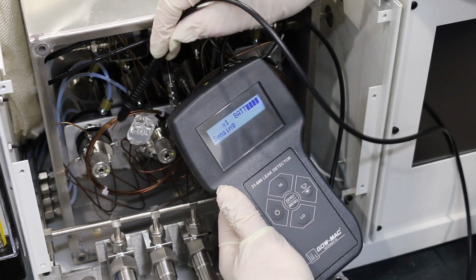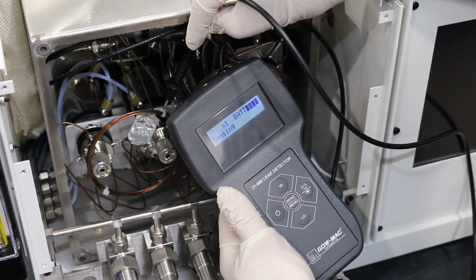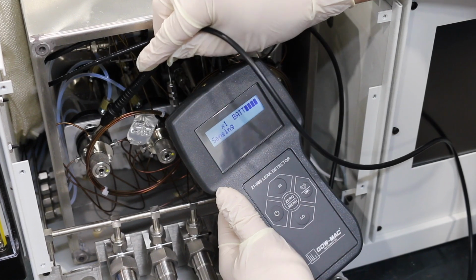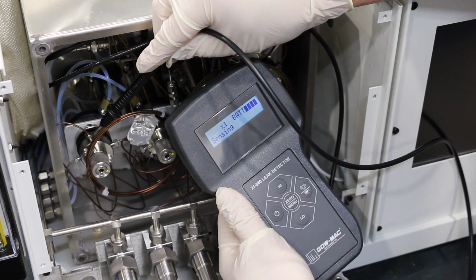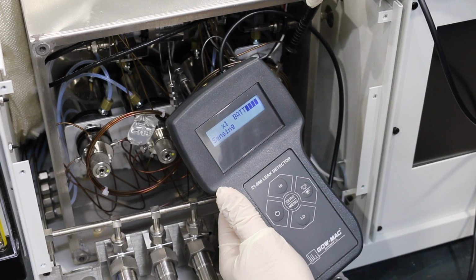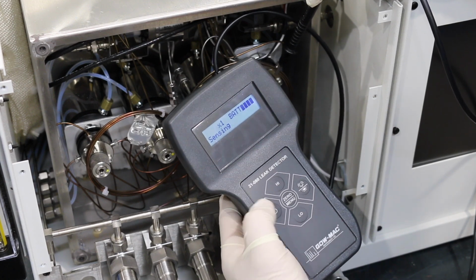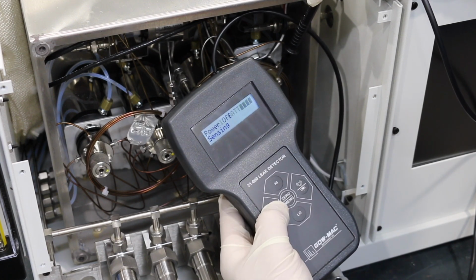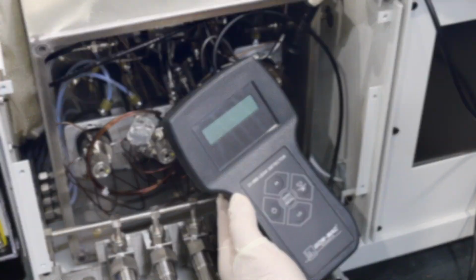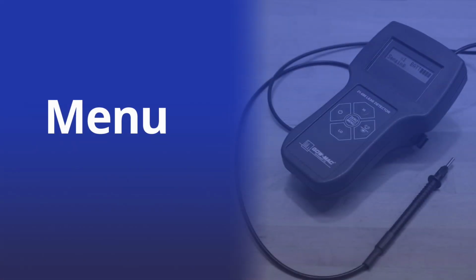7. When locating the smallest leaks in high range, the user should wear a glove on the hand holding the probe. Contaminants from the bare skin can be pulled in through the sampling probe. 8. To shut off the leak detector, press and hold the power button for 1 second. The long press. Menu.